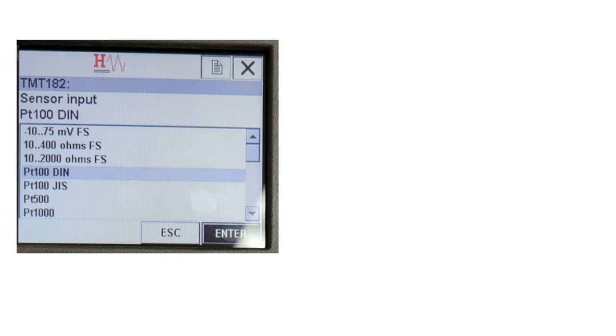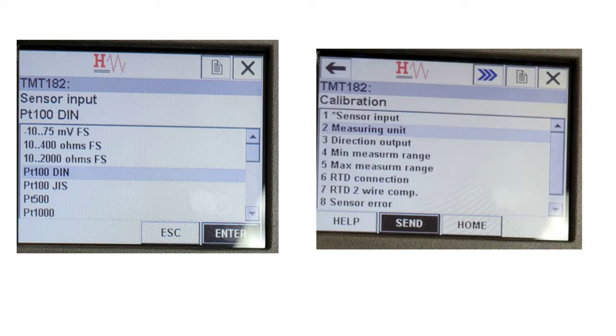In the Sensor Input menu, you will see different options such as PT100DIN, PT100JIS, PT500, PT1000, and others. In this example, a PT100DIN RTD has been connected. If you have connected a thermocouple, select the particular thermocouple from this menu. Select PT100DIN, then press the tab button twice to select Enter and press the Enter button. Once the sensor input is selected, choose the Send option from the bottom bar and press Enter to send the sensor input value to the temperature transmitter.